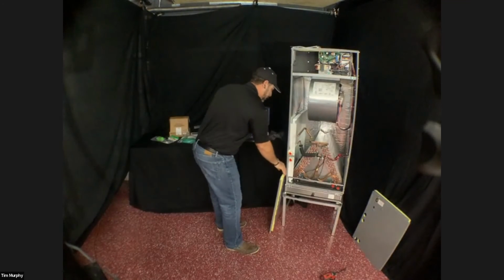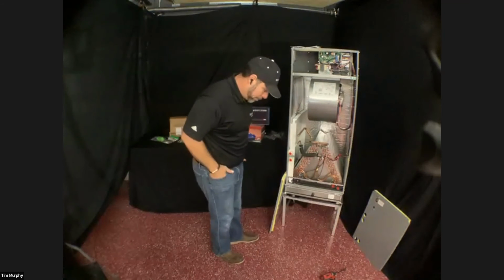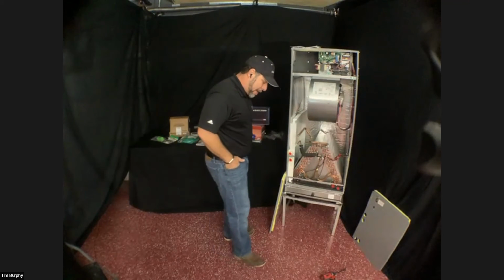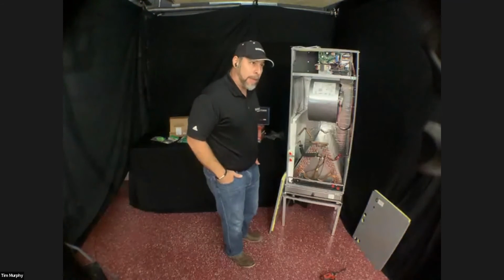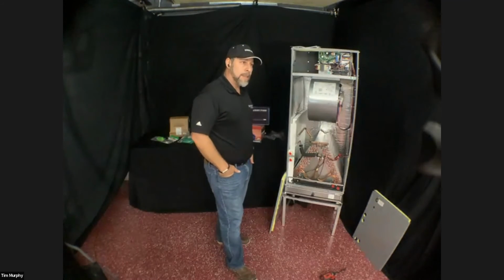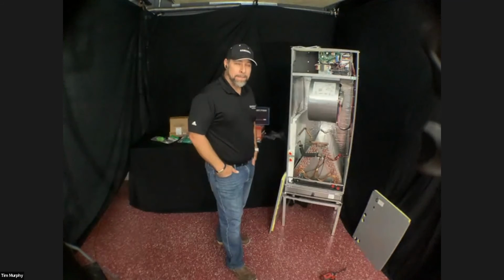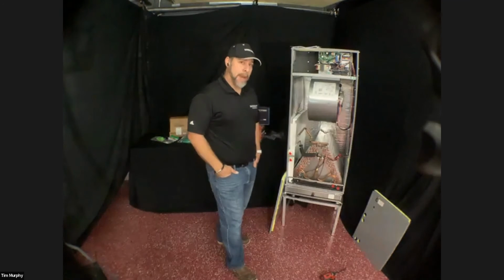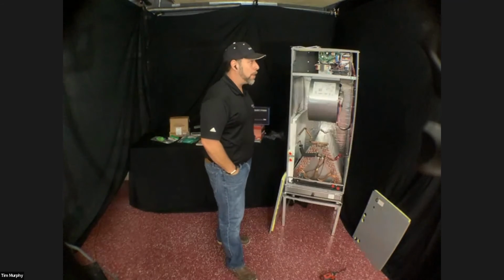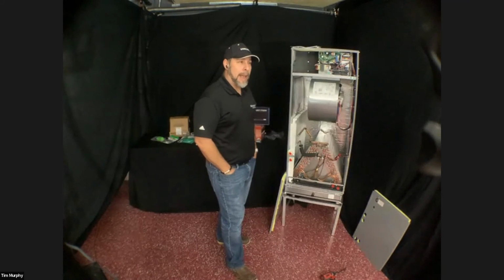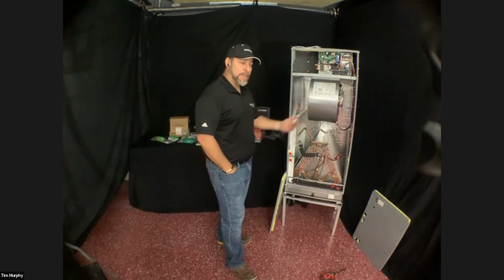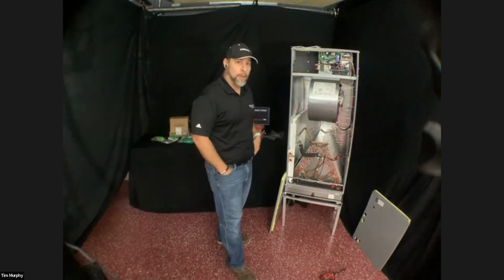Todd Sutherland is asking, is the outdoor coil micro channel? Yes, I believe the outdoor unit is microchannel, but I'd have to check when that change took place. When I read the submittal on the condenser, it does say it's a microchannel coil, aluminum microchannel. I haven't seen the newer ones, I know the older ones were still copper, but the submittal shows the new ones are going to be all microchannel aluminum.